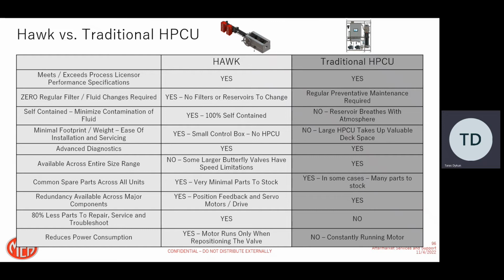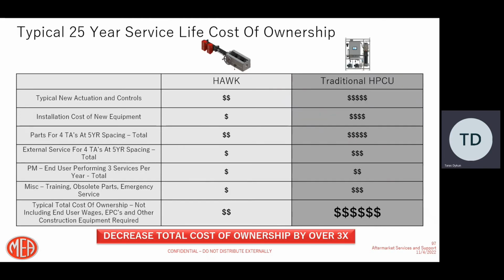80% less parts to repair, service, and troubleshoot. Hawk, yes. HPCU unfortunately has a lot more parts, and we estimate approximately 80% more parts compared to the Hawk type of actuator. Additionally, Hawk operates only when it is required to move, so you have a major reduction in power consumption, and HPCU runs motors constantly. With that being said, as you can see, there is a major difference between one and the other actuator system, and this also majorly affects the total cost of ownership of these units.